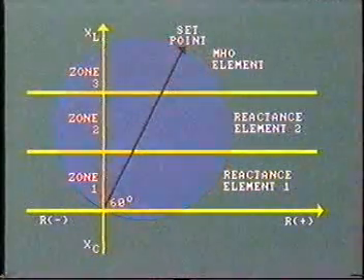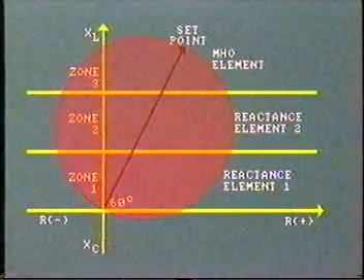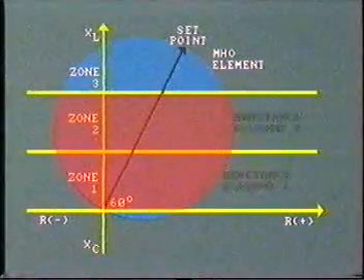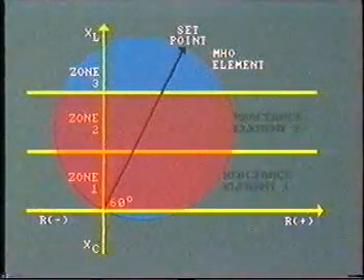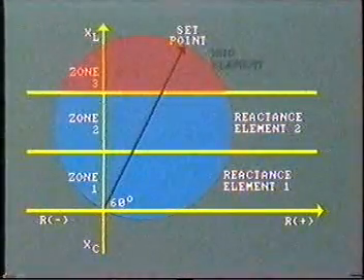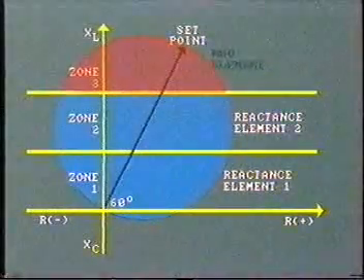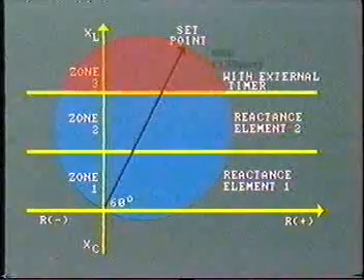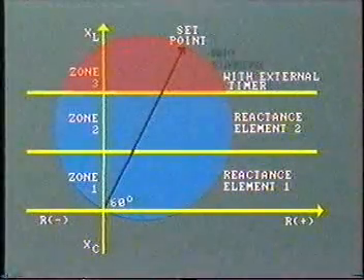The characteristic is shown on this diagram. There are two reactance elements, each protecting first and second zones. The circle diagram for the Mho element shows that it is set to protect the third zone. It includes an external timer to prevent early tripping.